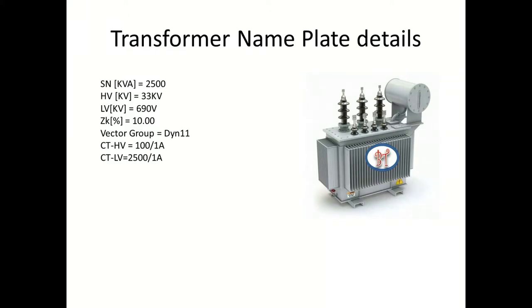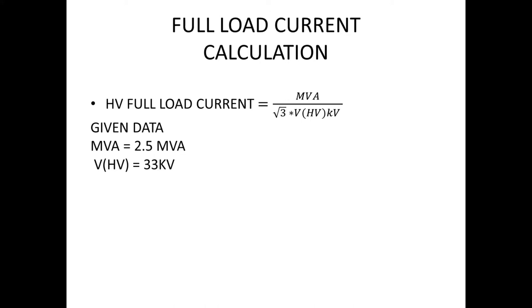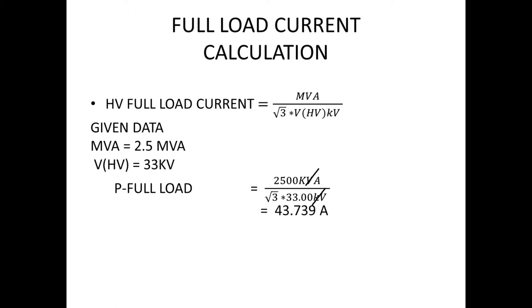The first number in the data is full load current, calculated using the formula: MVA divided by root 3 into voltage. For the HV side, voltage is 33 KV and MVA is 2.5. The formula gives 43.8 A, so full load current on the HV side is 43.8 A.